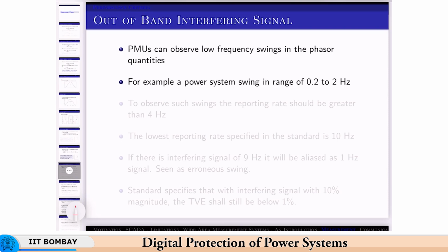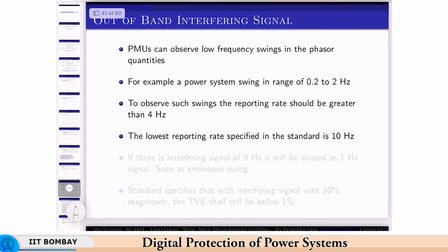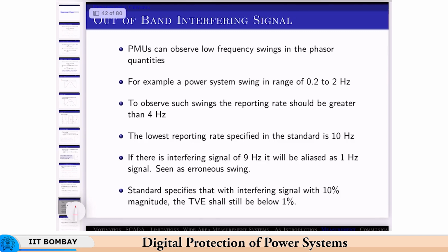And then we have seen the Nyquist criteria, and to observe such swings, the reporting rate should be greater than twice this. So, it should be greater than 4 hertz, and the lowest that the standard allows is 10 hertz. So, this can be comfortably observed. Okay. We also saw some aliasing effects in the initial parts when we saw the Nyquist criteria. Okay. So, here if there is an interfering signal of 9 hertz, it will be aliased as a 1 hertz signal. This can be seen as an erroneous swing.